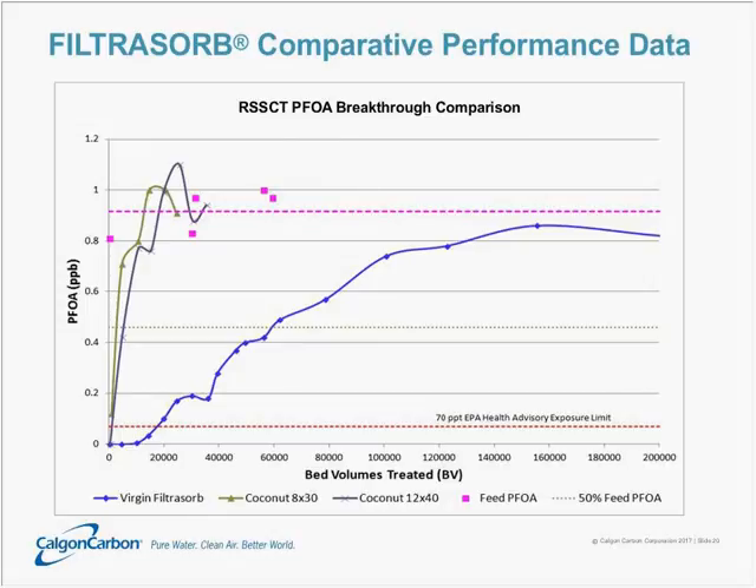This RSSCT compared three different activated carbon types — two coconut carbon types and one virgin Filtrasorb bituminous coal carbon. It simulated a 10-minute empty bed contact time with an influent concentration of PFOA of about 900 parts per trillion. The coconut carbons show breakthrough almost instantaneously, rapidly approaching the influent concentration after only a few thousand bed volumes. In contrast, the Filtrasorb product stays non-detect — below 2 nanograms per liter, or 2 PPT — for nearly 10,000 bed volumes, and only reaches the 70 PPT health advisory after 20,000 bed volumes.